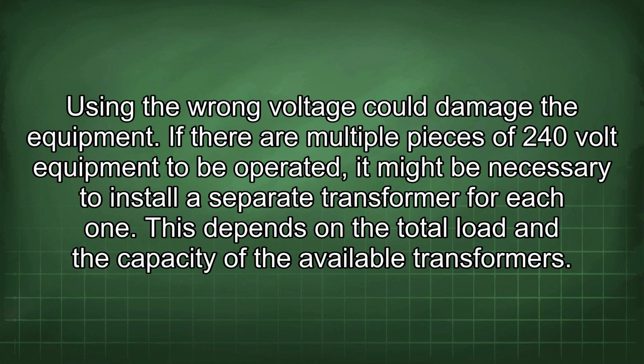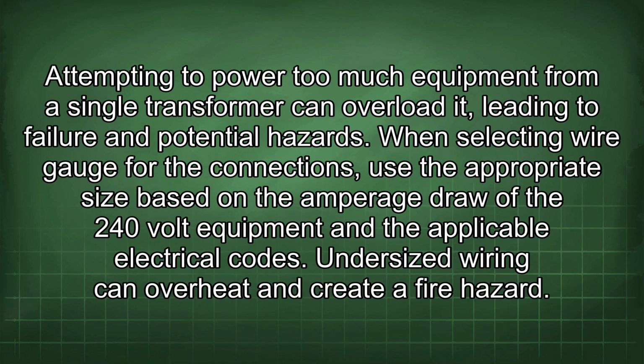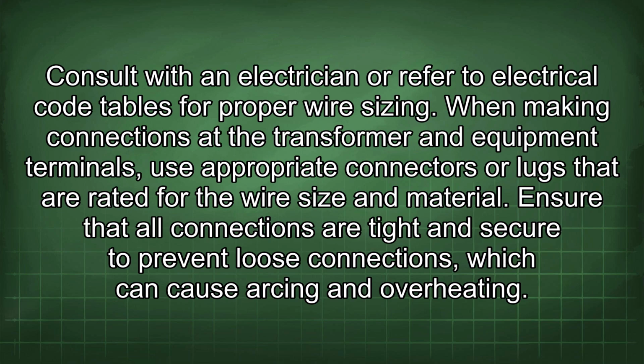If there are multiple pieces of 240-volt equipment to be operated, it might be necessary to install a separate transformer for each one. This depends on the total load and the capacity of the available transformers. Attempting to power too much equipment from a single transformer can overload it, leading to failure and potential hazards. When selecting wire gauge for the connections, use the appropriate size based on the amperage draw of the 240-volt equipment and the applicable electrical codes. Undersized wiring can overheat and create a fire hazard. Consult with an electrician or refer to electrical code tables for proper wire sizing.